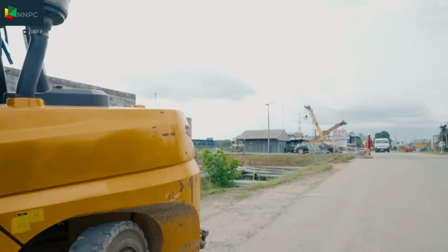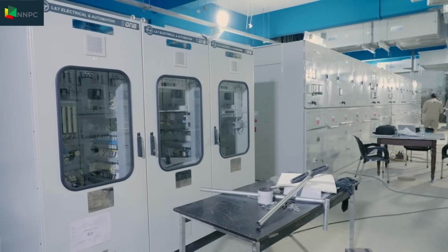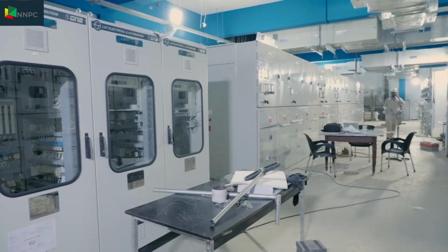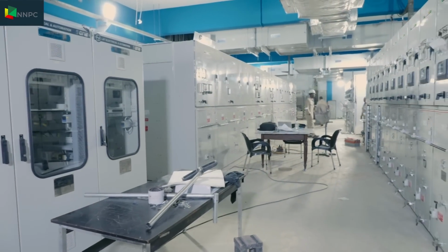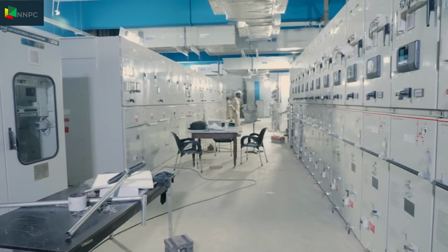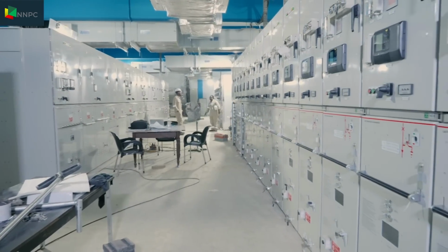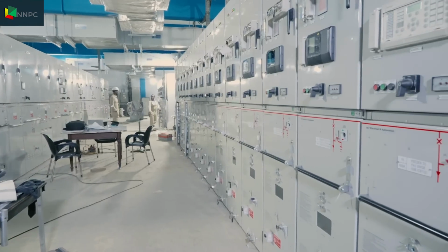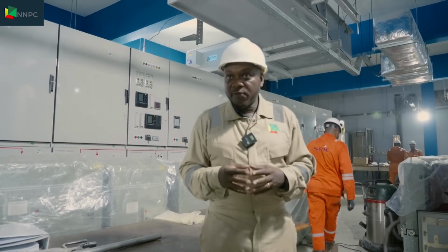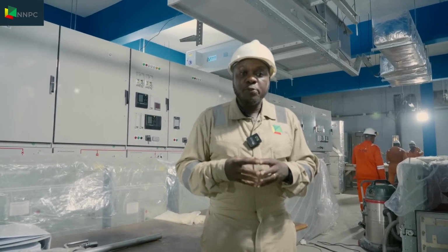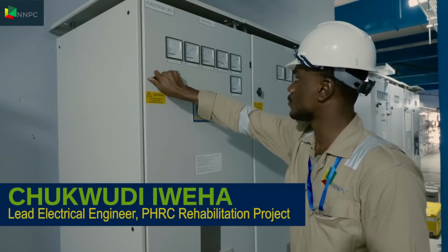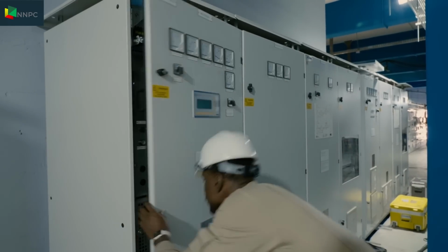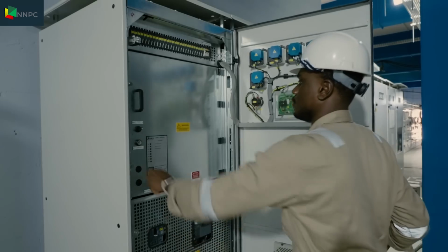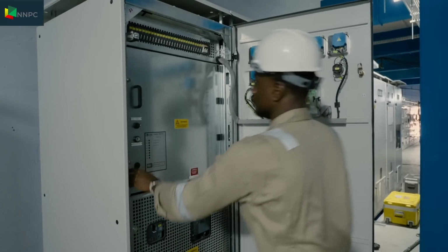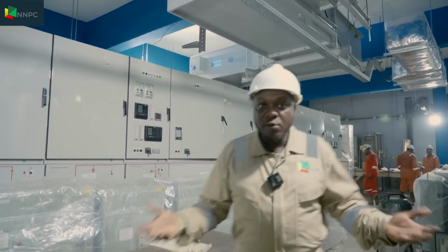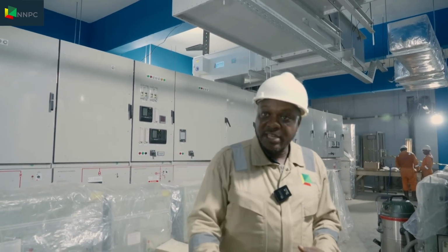Substation 1, which is the refinery's primary substation and powerhouse, will supply electricity to substations in the old and new refineries. It is designed to receive power from gas turbine generators. Right now we are at the testing phase, and we hope to finish the testing phase in a week, so that once we finish and we're very sure we can commission here, I'm very sure by the next time you come in less than 2 weeks' time, all the lights will be on and here will be up and energized. We call it energizing the substation.